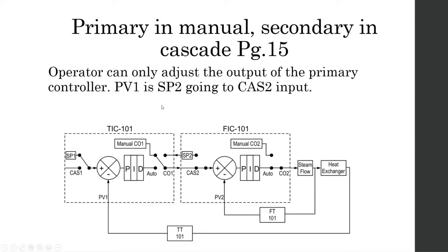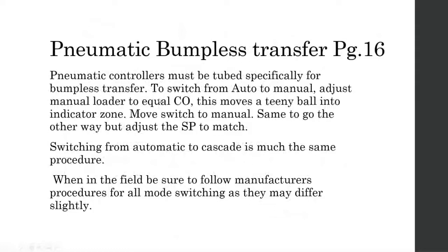So that's wonderful. Pulling out of the archives here, pneumatic bumpless transfer. So bumpless transfer isn't new. It's been around forever. It's important. We're going to just touch on pneumatics here real quickly. In order to do this pneumatically, the controllers have to be tubed specifically for bumpless transfer. In order to do the switch from auto to manual, there's a procedure which involves adjusting a manual loader in order to equal the controller outputs between the two controllers. And what happens is it moves a teeny little ball into this indicator zone.